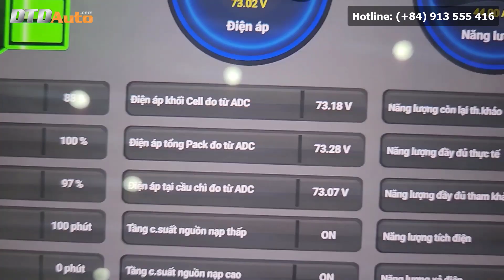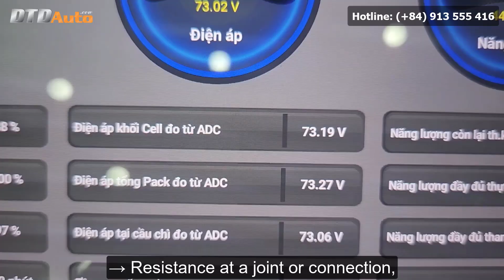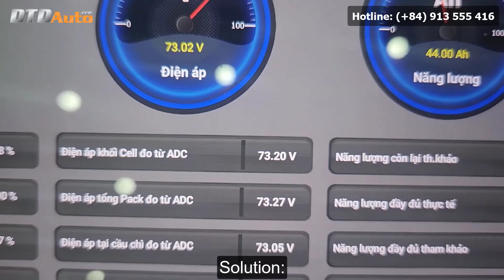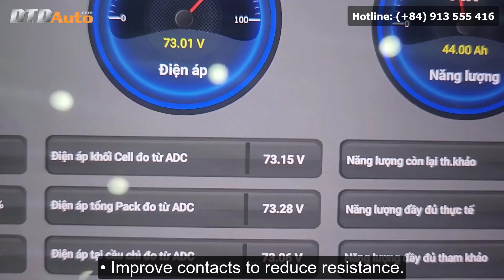Meaning: close values indicate good electrical contact with negligible contact resistance. Large differences indicate resistance at a joint or connection, causing power loss and heat. Solution: check, clean, and tighten connections; improve contacts to reduce resistance.